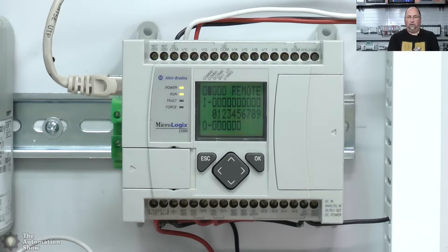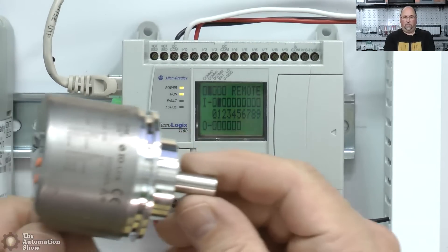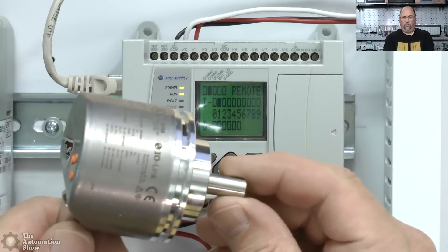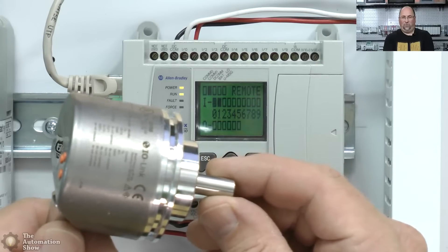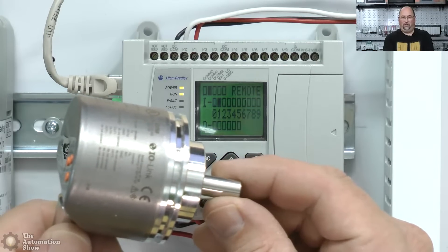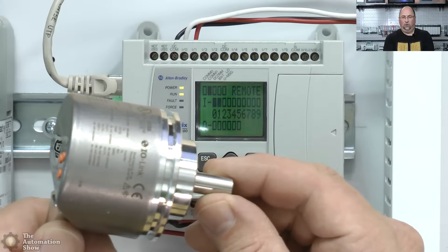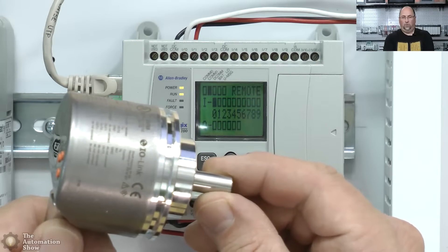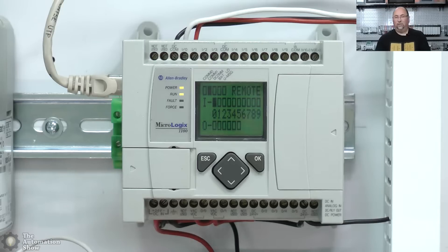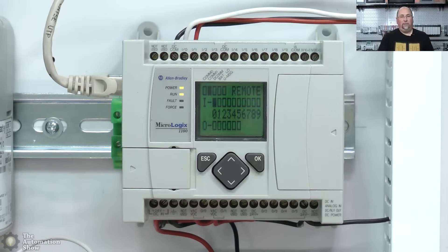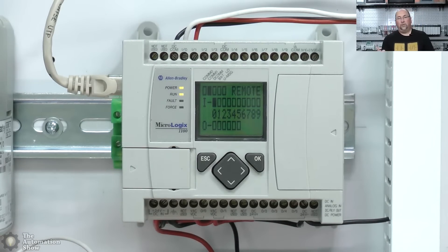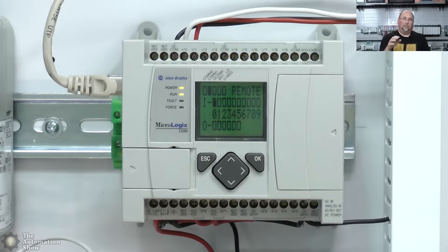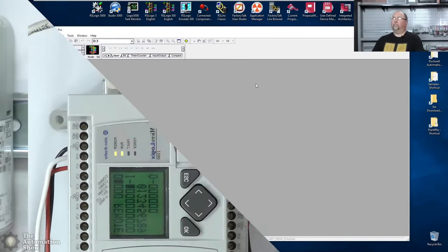But it does support four. And because I wanted to do pulse and direction, I've wired up A and B. So that'll give me a pulse and direction. Now, if I take the encoder here and I turn it, you can see zero one flickering on and off. Try to turn really slow. So we can see everything's wired up correctly. So now it's time to go over to the computer and actually set up the MicroLogix 1100.